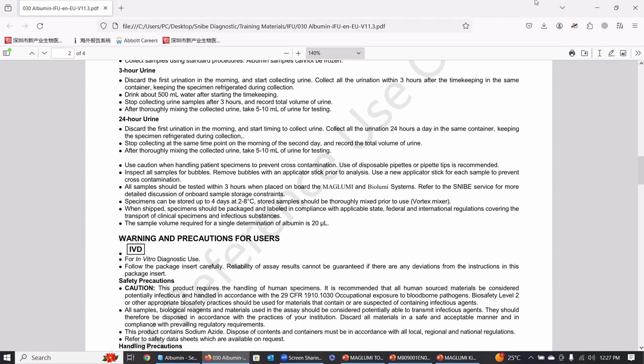But if I got an opportunity with a customer who is using microalbumin or beta 2 microglobulin, I would try these preservatives, because these analytes are usually from other companies' platforms. They are from the chemistry principle, but it doesn't mean that the preservative may not have an impact on the chemiluminescence. That needs to be validated, and I have to recommend it to the SNIBE headquarters.